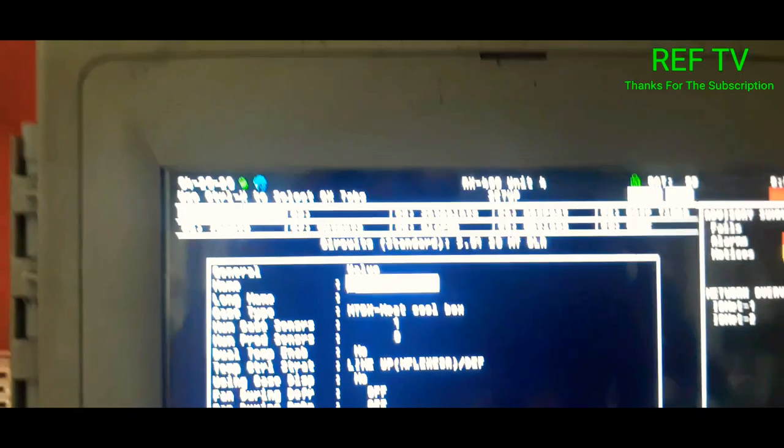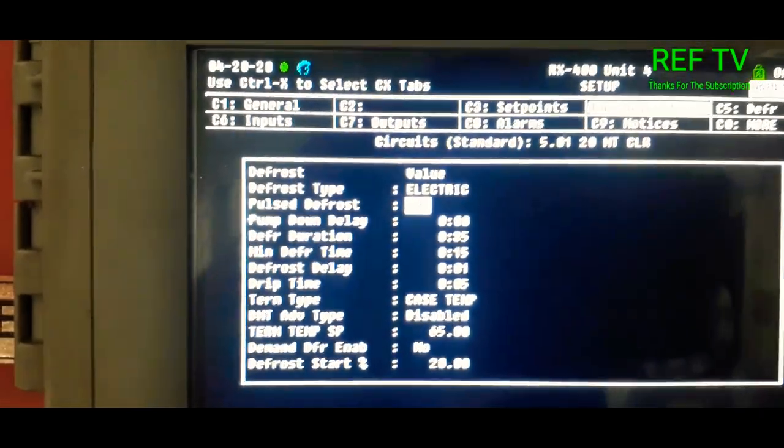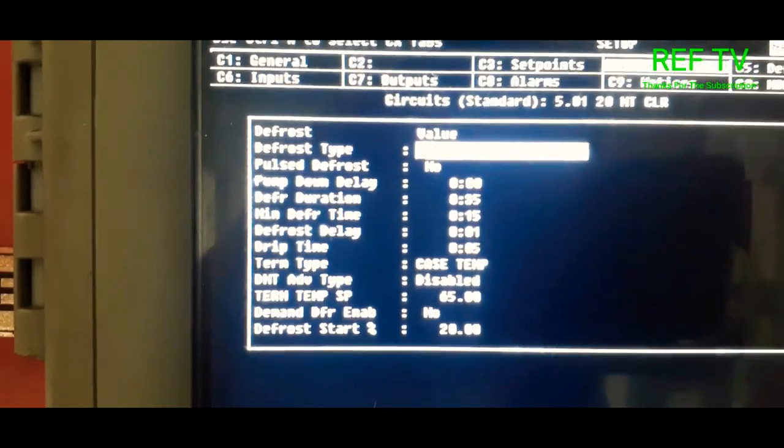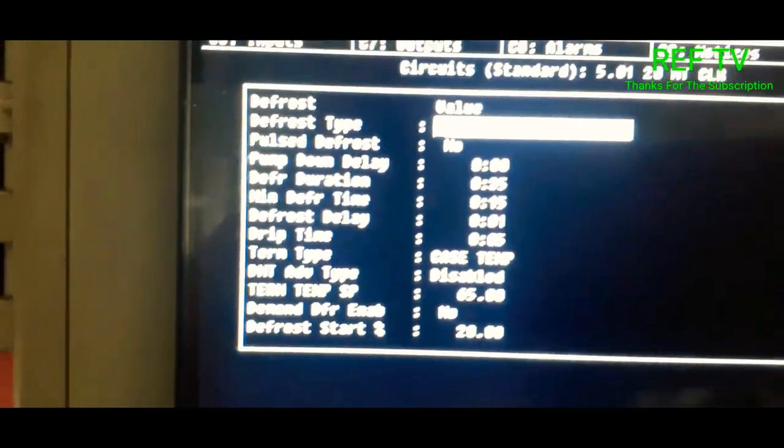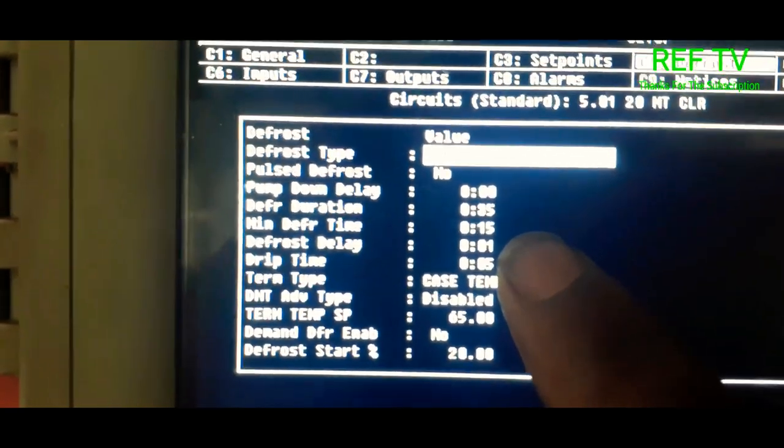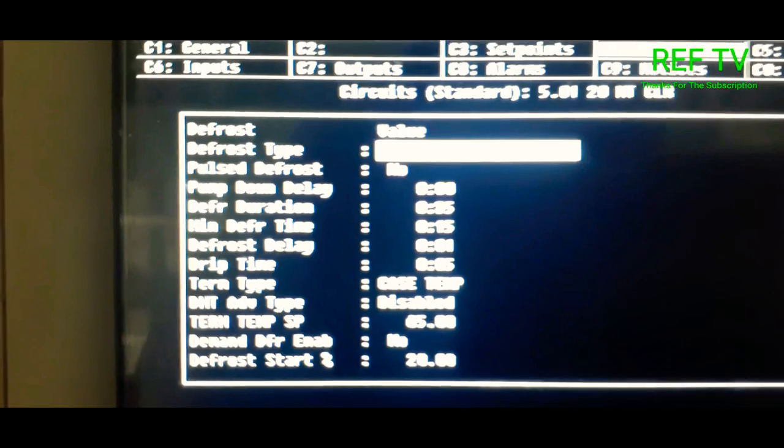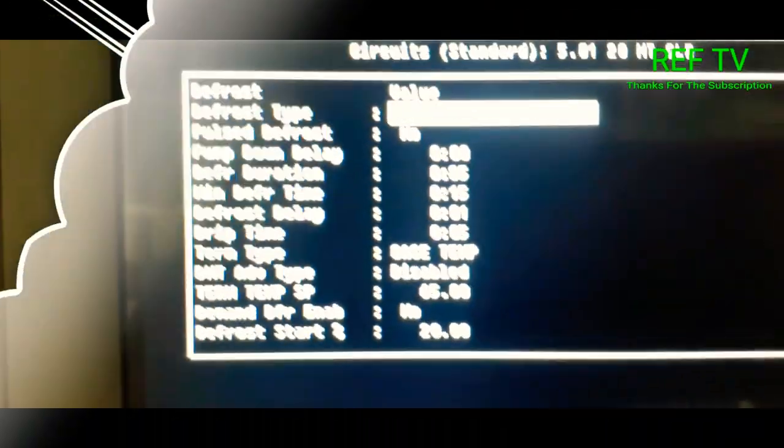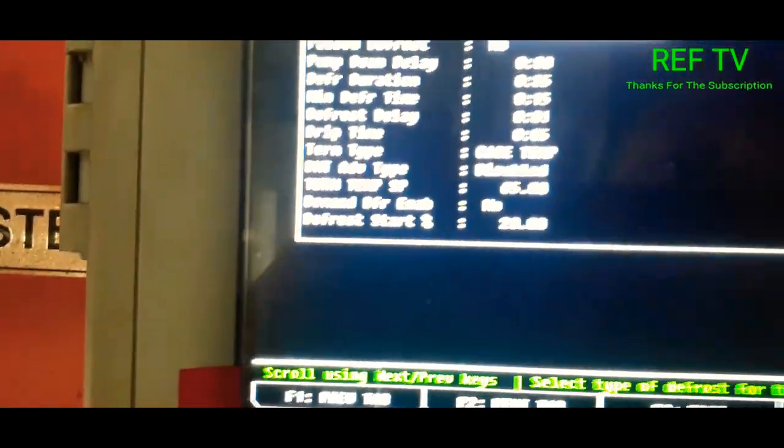Check our setup. We're set up for electric heat, 35 minute duration, 15 minute minimum, one minute defrost delay with a five minute drip. Set the terminator on case temp of 65 degrees. Let's just go and check our heaters.